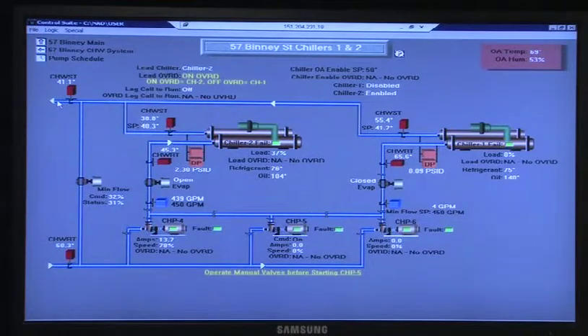That's supplying the building chilled water, which we'll look at on the next screen. We'll go backwards a little bit. Chilled water return from the building is 62.2 degrees. It comes back through. You have 3 sets of pumps, same as the condensing water pumps. The middle pump is a manual operation. Pump 4 and pump 6 are automated and commanded.